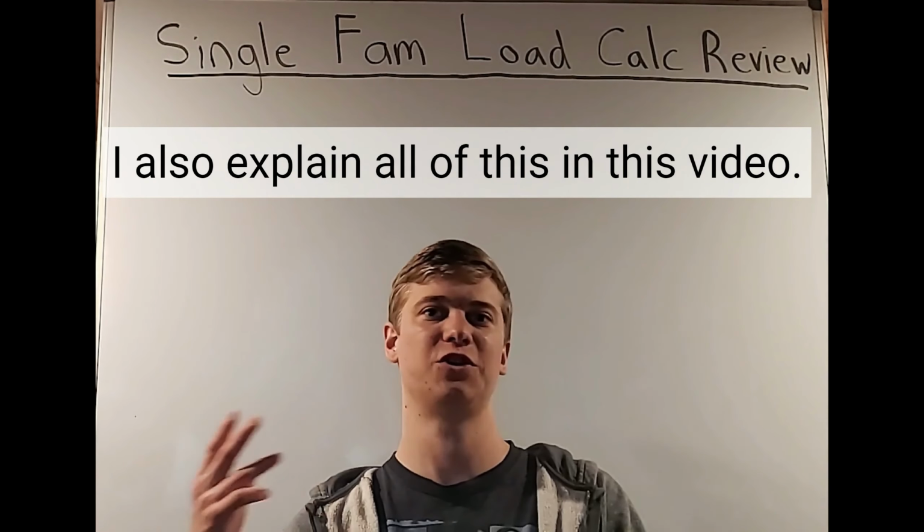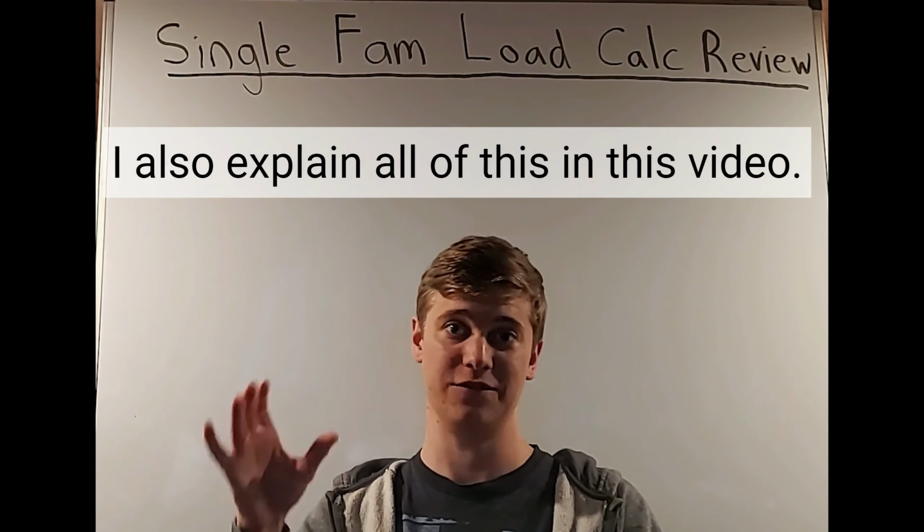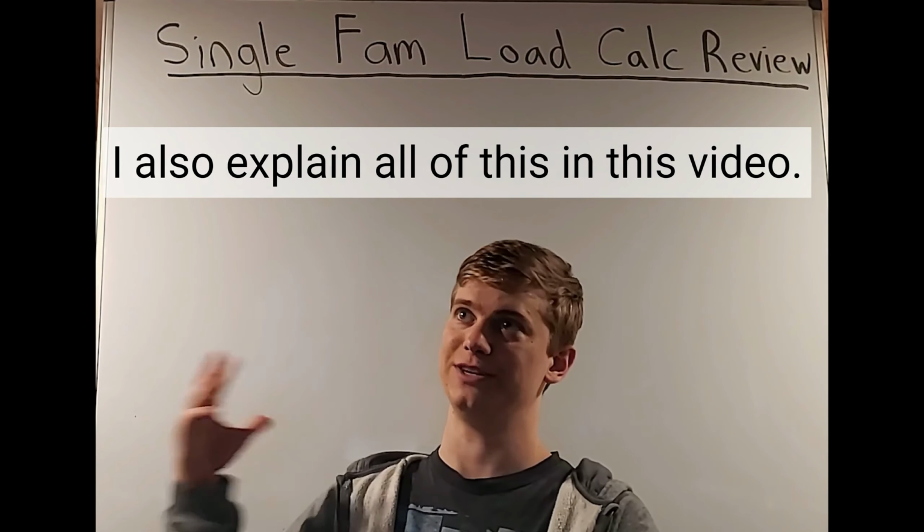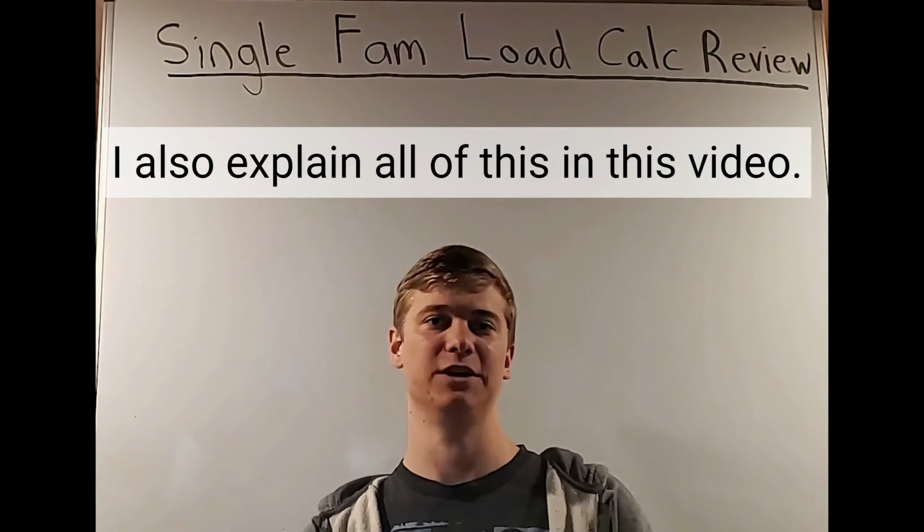And then I also show you how to find out the size of wire. You might think you just go to table 310.16, but I show you that normally you're going to be using table 310.12. It's all explained in that video. It's a good video. And since that was part 2, that was still the single family dwelling of the residential load calculations. And that's where I was showing you that 25% of the largest motor.